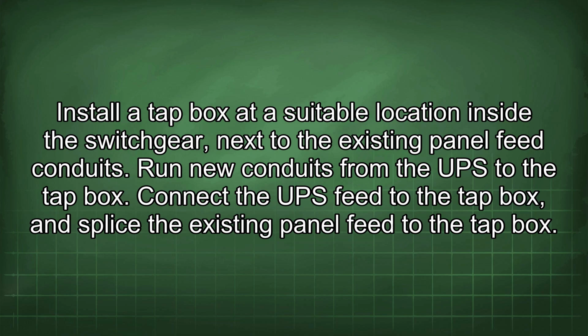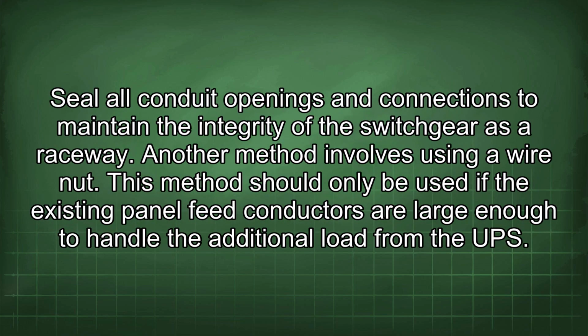Run new conduits from the UPS to the tap box. Connect the UPS feed to the tap box and splice the existing panel feed to the tap box. Seal all conduit openings and connections to maintain the integrity of the switchgear as a raceway.